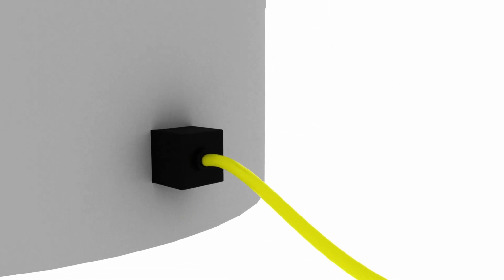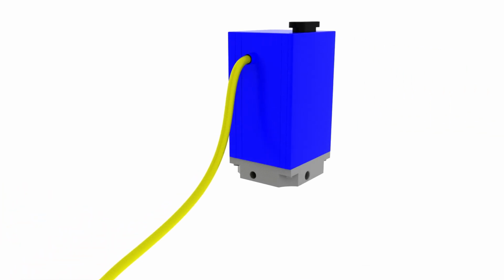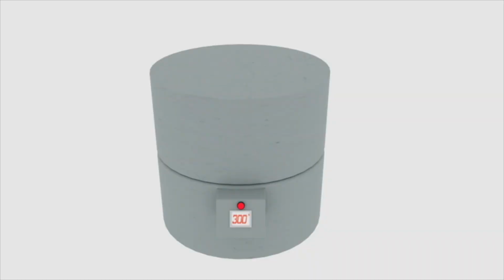Dome pressure is based on closed-loop feedback from the external DST transducer measuring steam output pressure in the curing cavity. Control of steam set pressure equals temperature control.